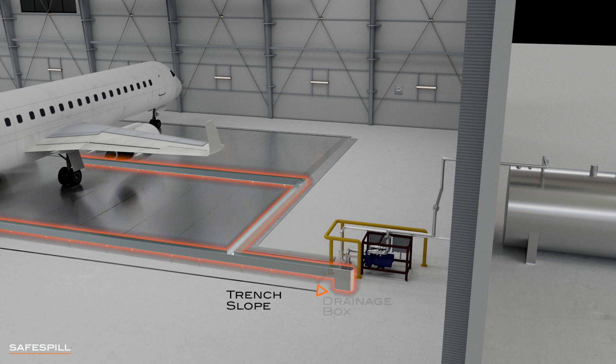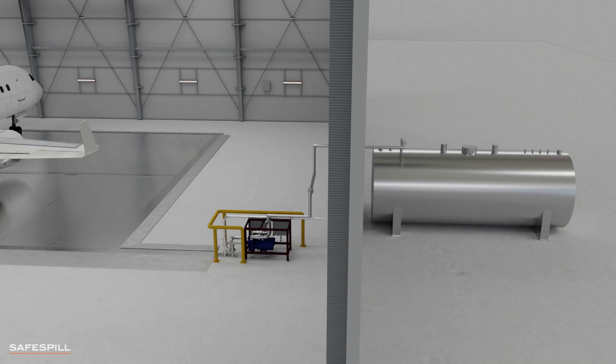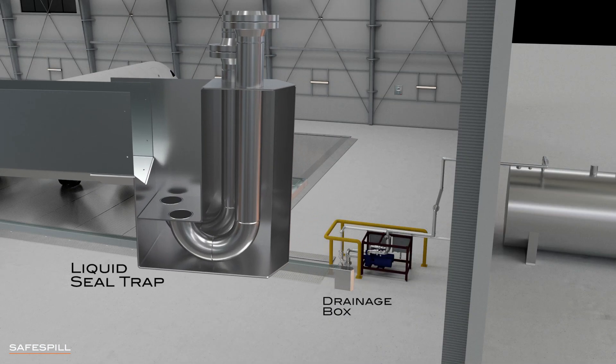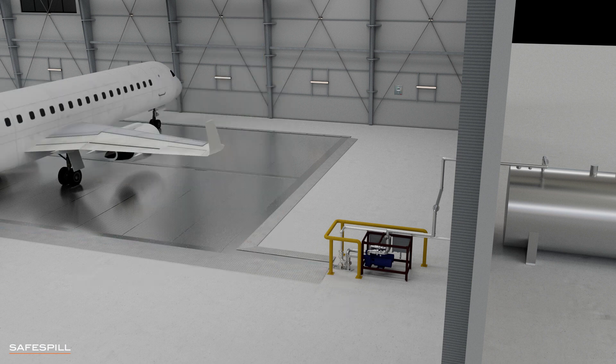The floor uses the existing slope of the hangar slab to drain spilled liquids through channels into covered trenches. The trenches slope outwards into a drainage box, ensuring all liquids are removed from the floor. Sensors activate pumps to extract the spill out of the drainage box, typically into an exterior containment tank. A liquid seal trap ensures that no ignited vapors travel through piping to the tank.